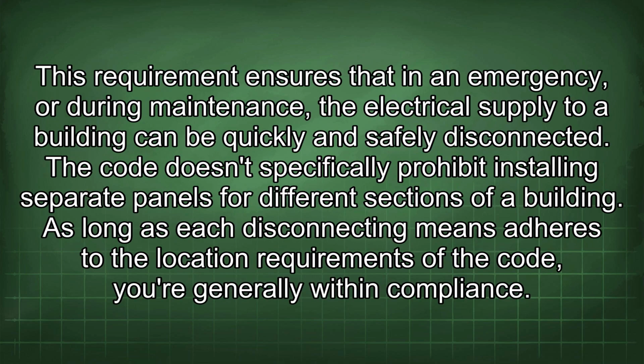This requirement ensures that in an emergency, or during maintenance, the electrical supply to a building can be quickly and safely disconnected. The code doesn't specifically prohibit installing separate panels for different sections of a building. As long as each disconnecting means adheres to the location requirements of the code, you're generally within compliance.